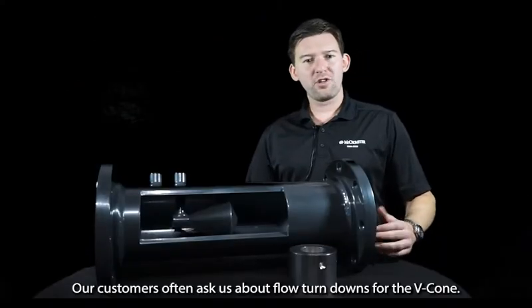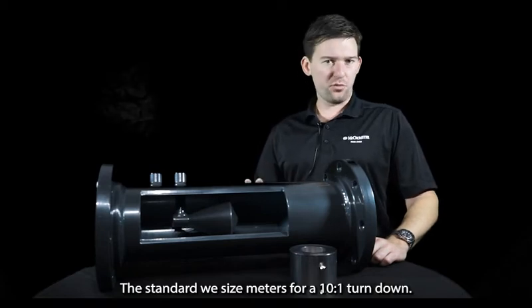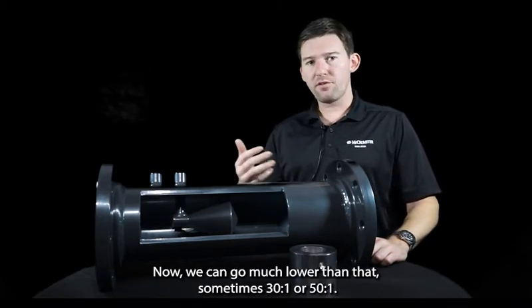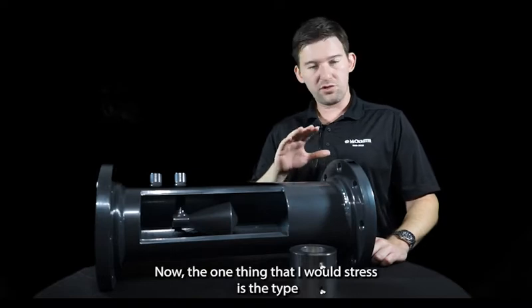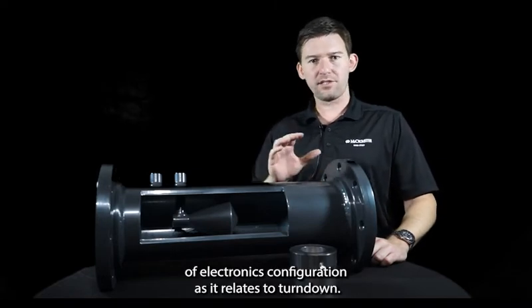Our customers often ask us about flow turndowns for the V-Cone. Standard, we size meters for a 10 to 1 turndown. Now we can go much lower than that — sometimes 30 to 1 or 50 to 1. It really depends on the conditions that you have and are able to provide us. The one thing I would stress is the type of electronics configuration as it relates to turndown.